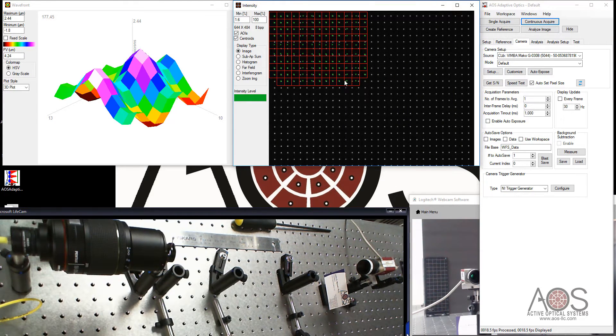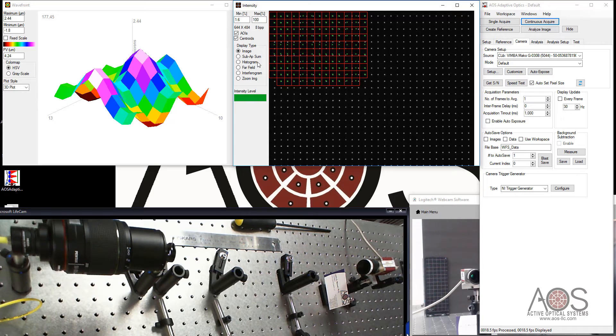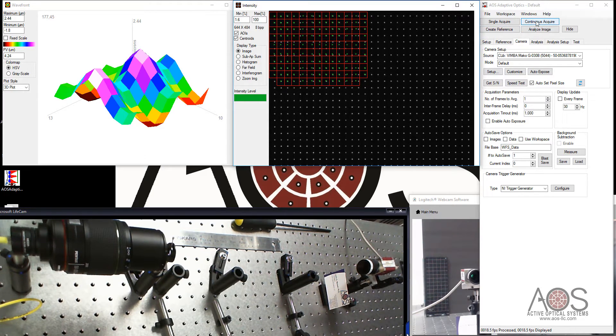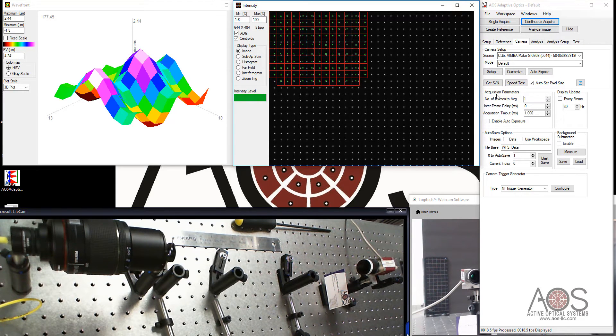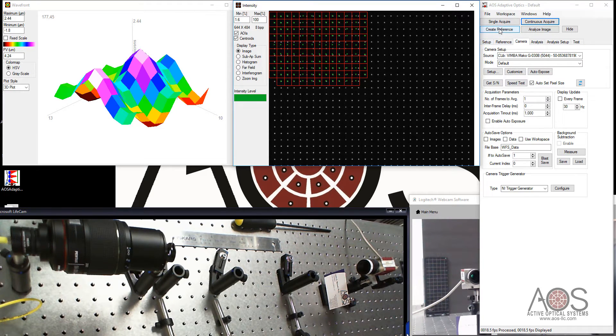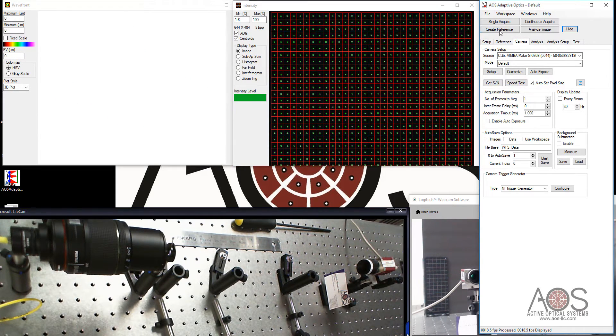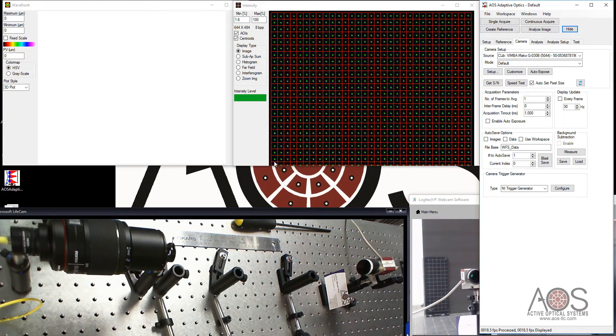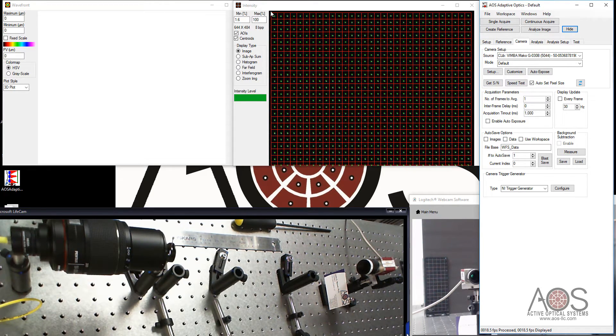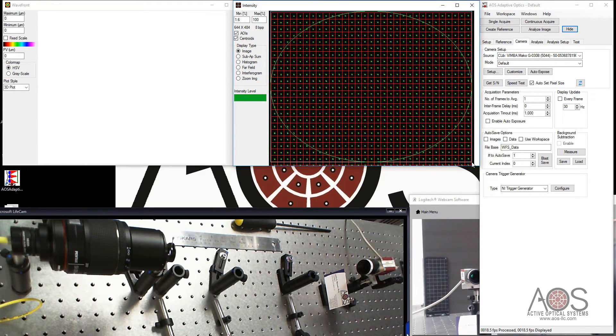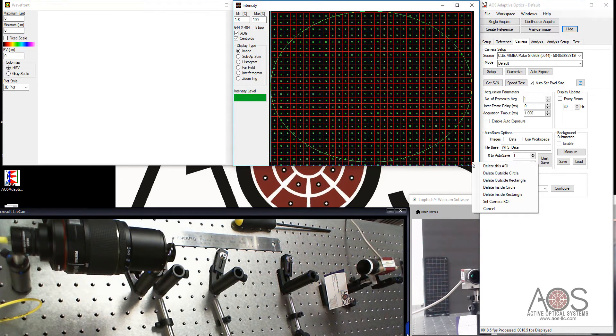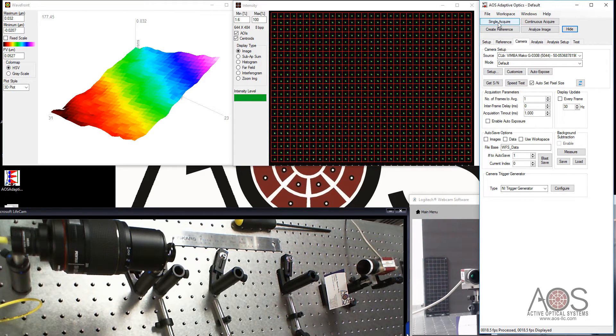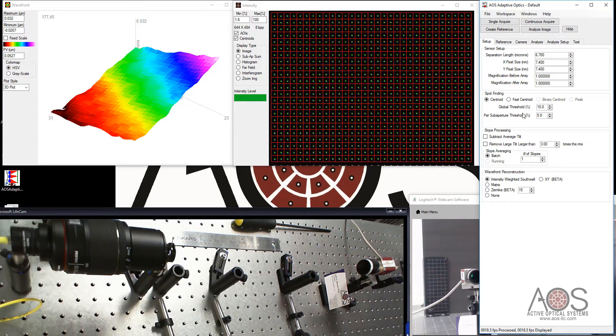That looks a little better in that 90 range. This is the default set of AOIs that comes up with the software. I'm going to go in and create a new reference here since I've got a collimated beam illuminating the wavefront sensor. I have this iris open as far as it will go right now. I'll click on Create Reference. Again, I've got an issue, just like I did in the last video, of these AOIs near the edges being suspect. So I'll go in, right-click and drag, and say Delete Outside Rectangle.